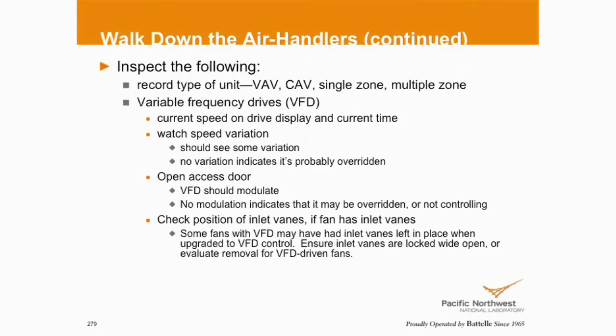If I've got inlet vanes, anybody have fans with inlet vanes still? Oh. Groan. You have my sympathy. Not for long. So if I have inlet vanes and I put a VFD on the fan, do I leave the inlet vanes in and lock them wide open, or do I remove the inlet vanes? You do either or. Somebody said get rid of them.